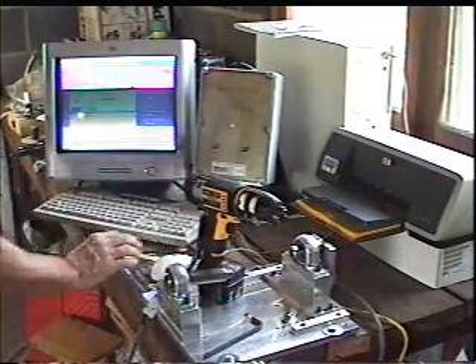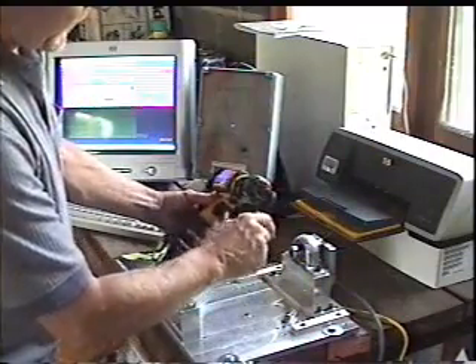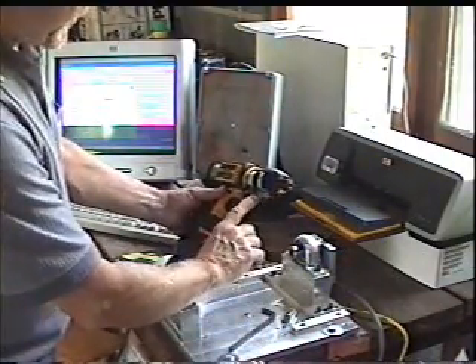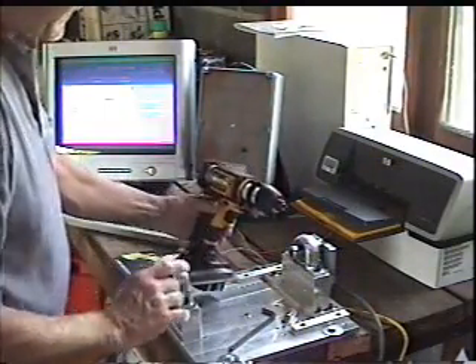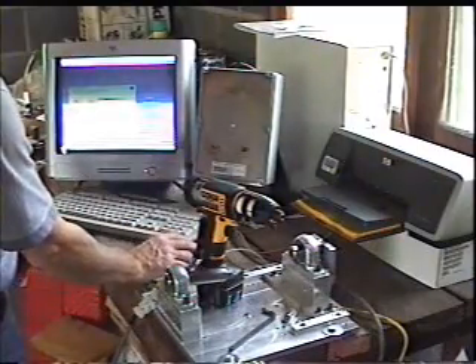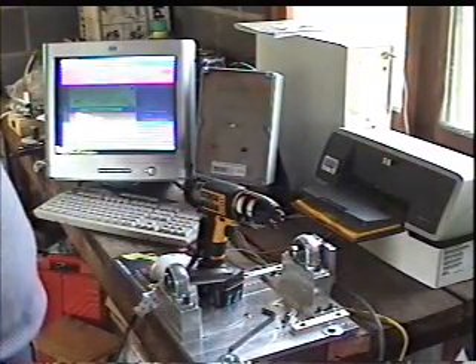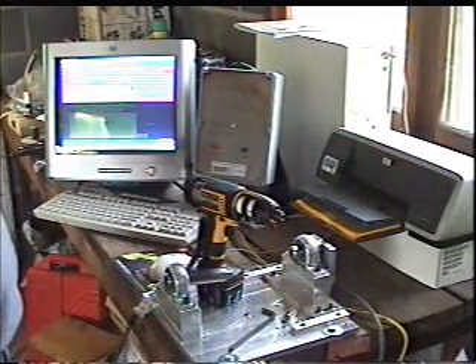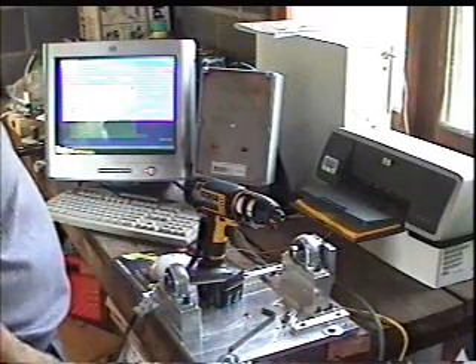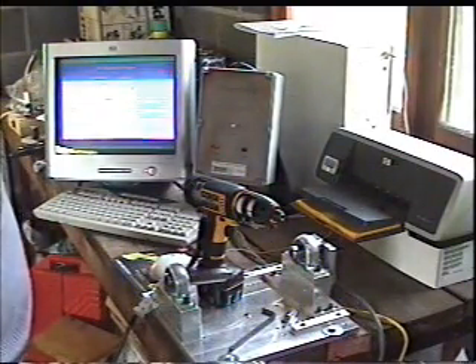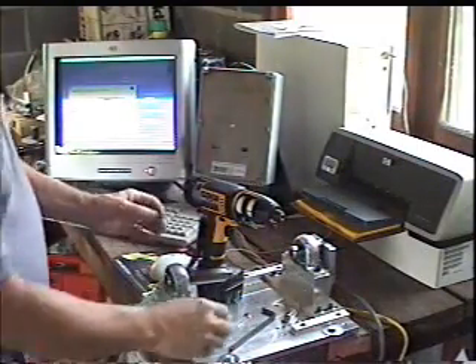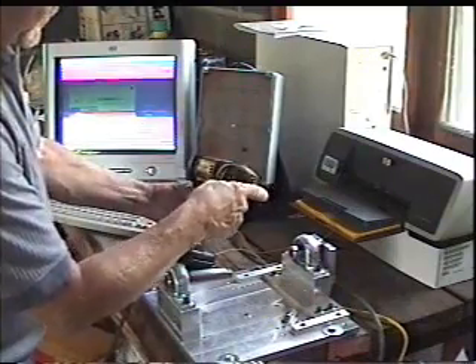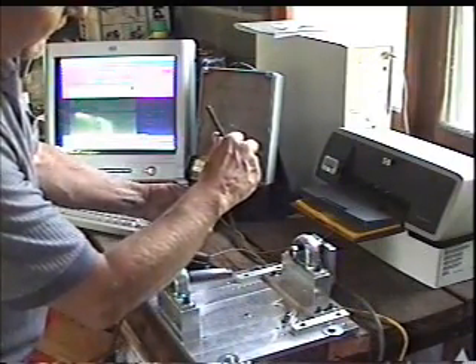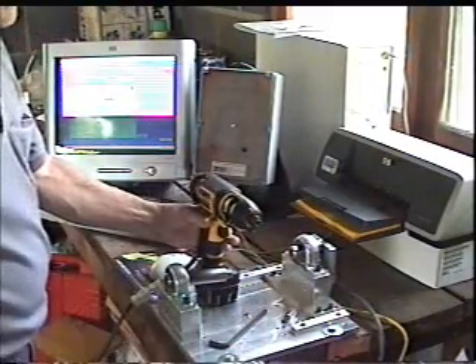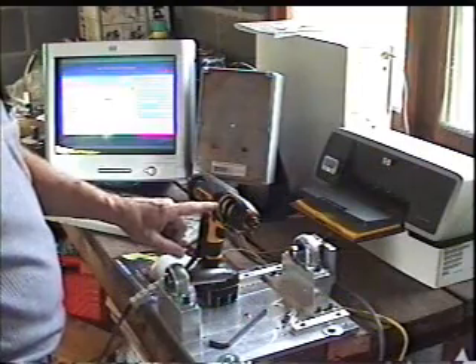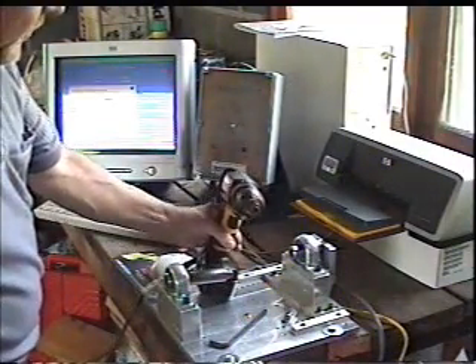and select calibrate, and right now there's no overlap in the discs, so there's no light coming from the emitter side to the detector side of the sensor. I'll select OK, and now it's doing a 10-second timeout looking at the detection system. And now it's asking me to apply a calibration torque of 3 Newton meters, and for example, we'll open up the slots in the disc so they're fully overlapped with the input side disc to the output side disc, and now they're fully overlapped.